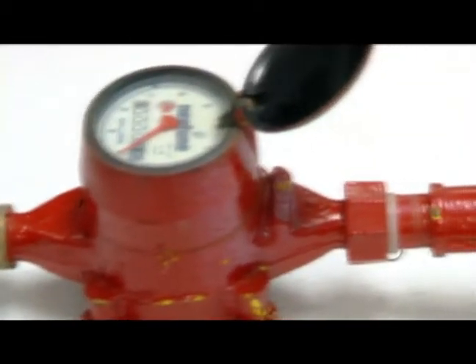I'm going to show you a picture of it in a few minutes. What's happened over the past several months is there have been thefts of a particular piece of this backflow preventer. The caps come off and the connections get damaged, the threads get damaged, so the fire department can't tie into them to feed the sprinkler system. Or kids come along and throw rocks or debris in there, and it delays our ability to get water on the fire.